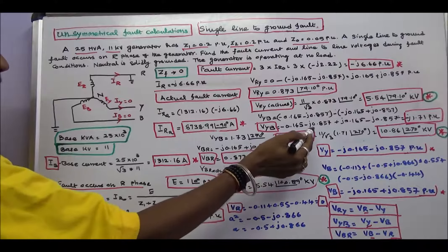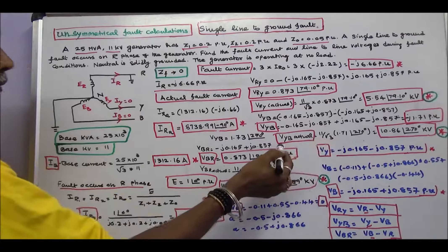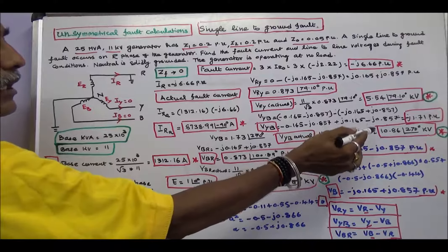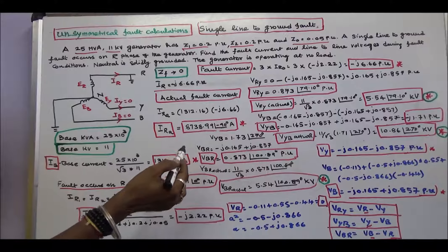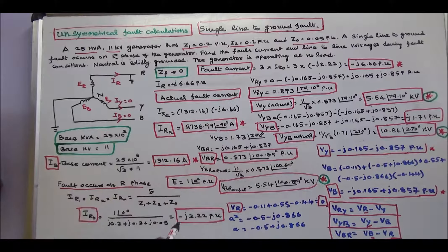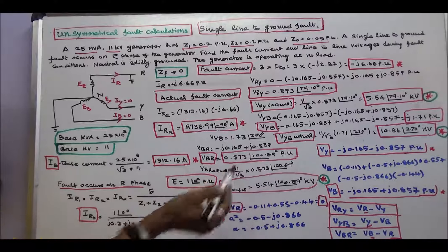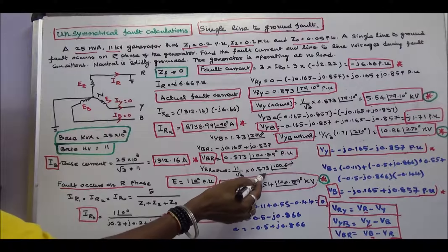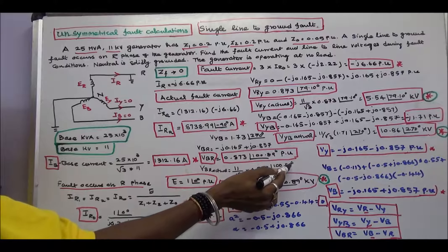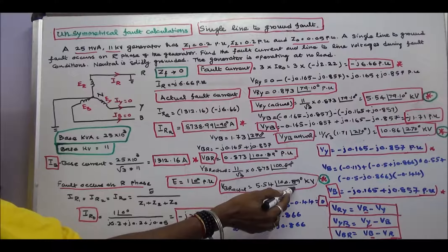VRY actual equals 11 divided by root 3 into 0.873 angle 79.10 degrees, which equals 5.54 angle 79.10 degrees KV. VYB equals VY minus VB, which equals minus j 1.71 per unit, corresponding to 270 degrees. Therefore VYB actual equals 11 divided by root 3 into 1.71 angle 270 degrees, which equals 10.86 angle 270 degrees KV. VBR equals VB minus VR, where VR is 0, giving VBR equal to 0.873 angle 100.89 degrees per unit. VBR actual equals 5.54 angle 100.89 degrees KV.